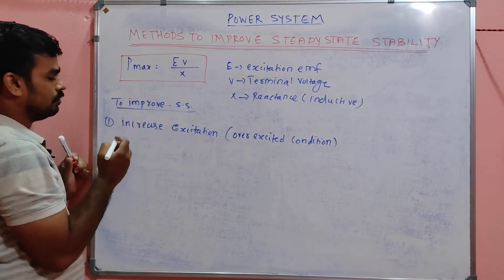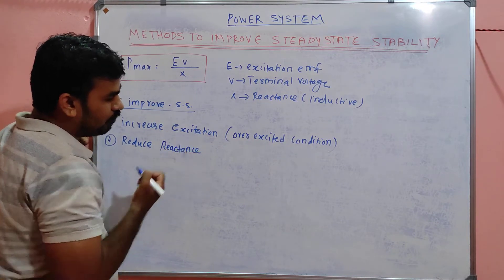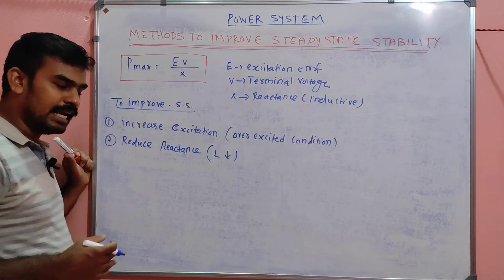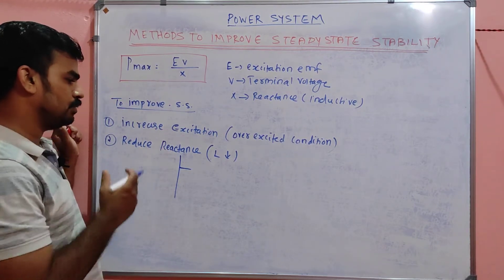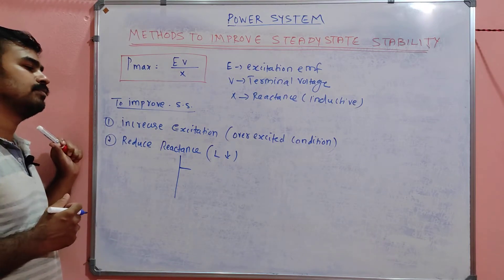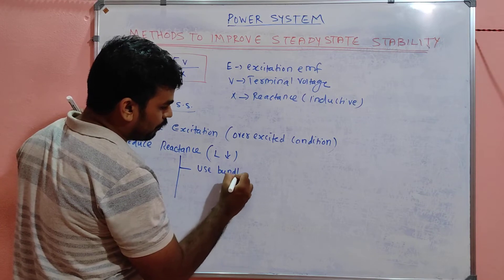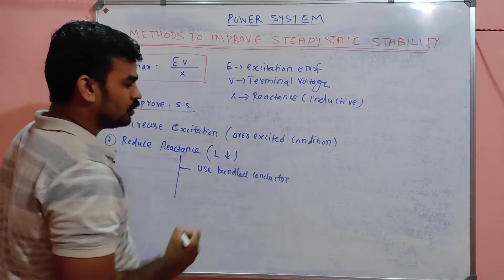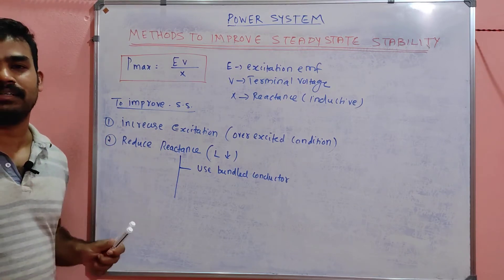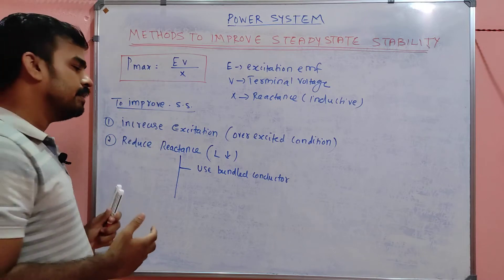The next very important method to improve the steady state limit is to reduce reactance — we should decrease L. One way to decrease L is to use bundled conductors. If you use bundled conductors, there will be cancellation of inductance due to the neighboring conductors, so the effective L will be reduced. If L is reduced, X is reduced, and P_max will be increased.